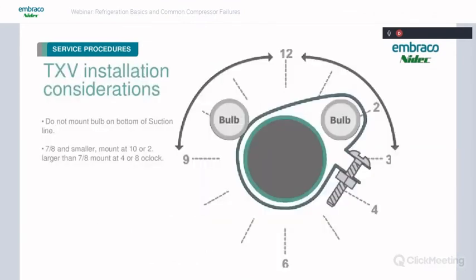So talking about that bulb being the throttle of the TXV valve, we want to make sure it's mounted correctly. Most of your manufacturers are suggesting 10 and 2. We never want to mount it on the bottom where oil or liquid could be giving you a bad temperature reading. So either 10 or 2 is typically where you want to mount it. If you have a weird application where you're adding an aftermarket TXV valve or something like that, it's highly recommended to contact the manufacturer of the TXV valve and ask them for a recommendation where to mount it.